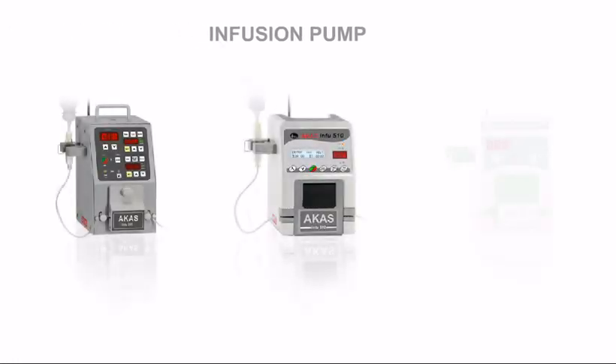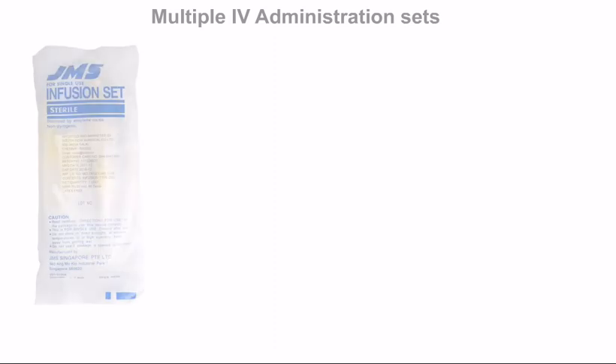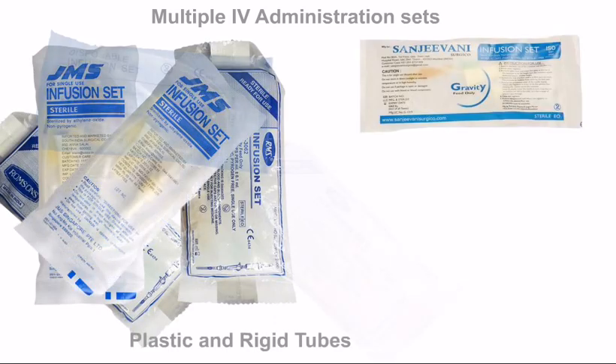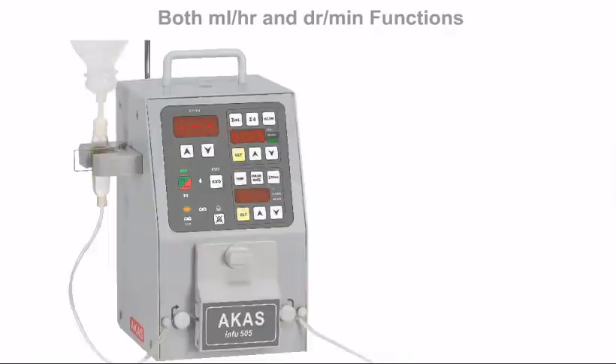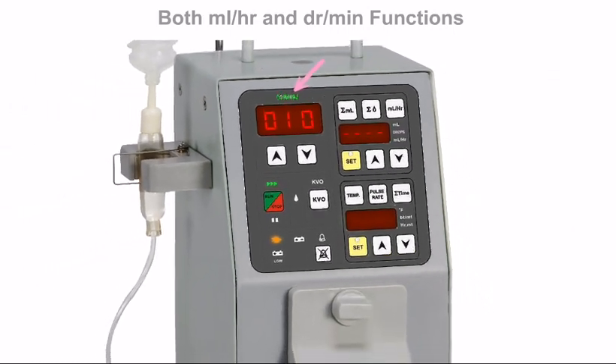Infusion Pump. If you are going to invest in an infusion pump, then the next 3 minutes of video presentation will help you take the right decision. AKAS infusion pumps are designed to accept all types of IV tubing. Even rigid plastic tubes can be used and still maintain accuracy of the set drop rate. Flow rates can be set in milliliters per hour or drops per minute.